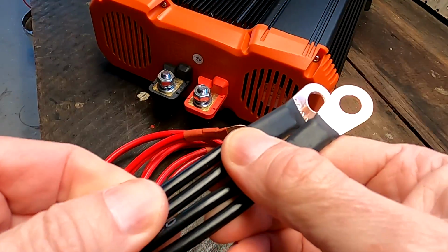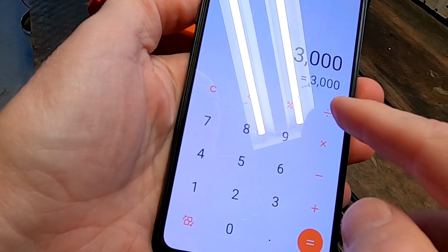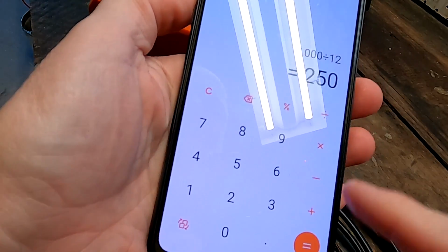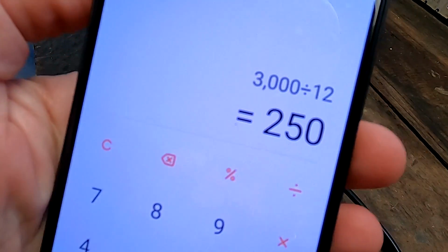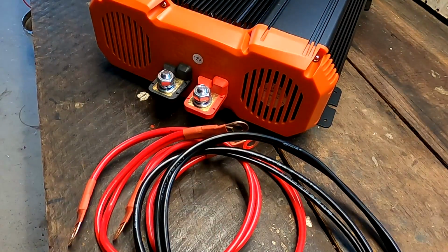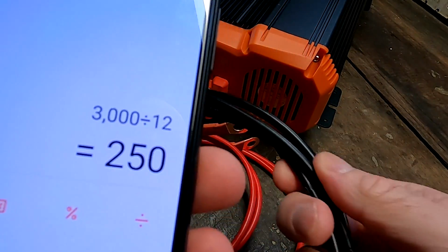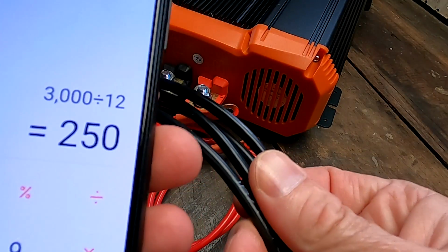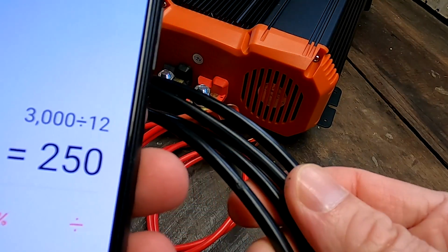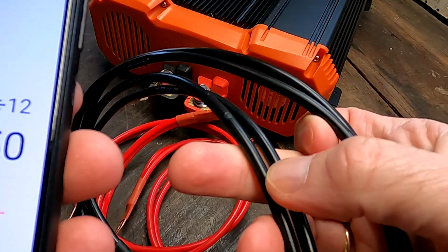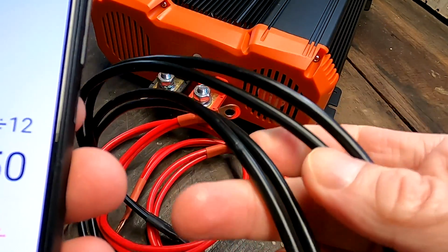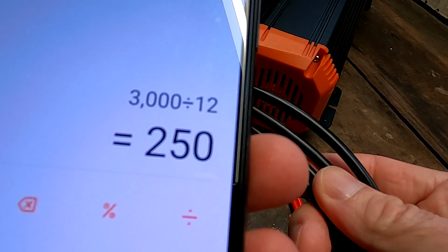That's 160 amps total carrying capacity with the cables they deliver with the inverter, and we have 4 of them in parallel. But 3000 divided by 12 is 250 amps, which is what the inverter can actually pull from your battery. For that, 160 amps is a bit low I would say - there are probably 100 amps missing, so we would need another pair of these cables to make it for 250 amps. The cables they deliver with these inverters are always too small - I would not trust such a cable for 100 amps continuous current.